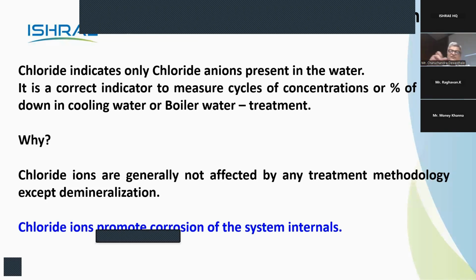For example, suppose your inlet water has a chloride of 20 and your outlet water is 300. So you are giving blow down there. You calculate that it is 300 - how many times did this 20 get multiplied to make it 300? About 15 times, meaning the blow down is about 5 to 7%. In case I have to decrease that blow down, I make it 20 times the multiplication, so 20 into 20 is 400. So that value of chloride into cooling water becomes the criteria.